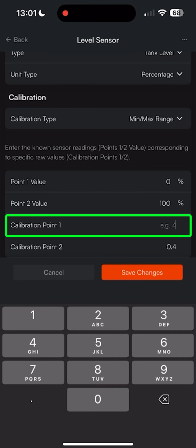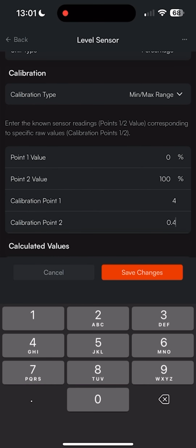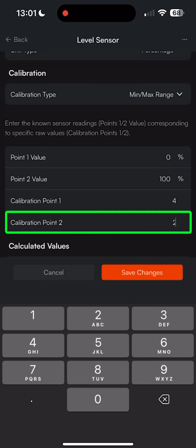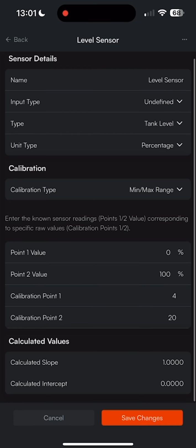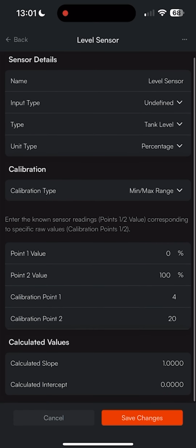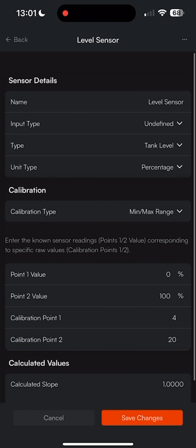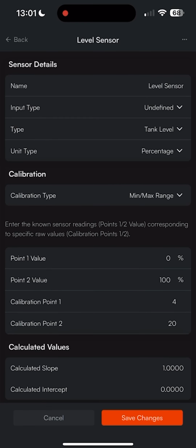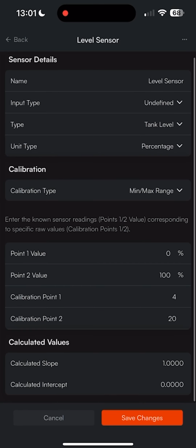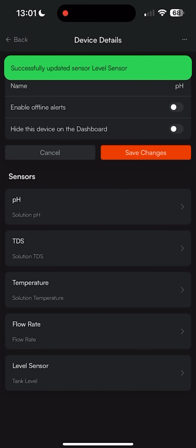In this case, this is a 4 to 20 milliamp sensor, so calibration point 1 would be 4 milliamps, and calibration point 2 would be 20 milliamps. This will create a default equation where the sensor will read 0% at 4 milliamps and 100% at 20 milliamps. All that's left is to save changes for this type of calibration, and these changes would get pushed to the controller itself.